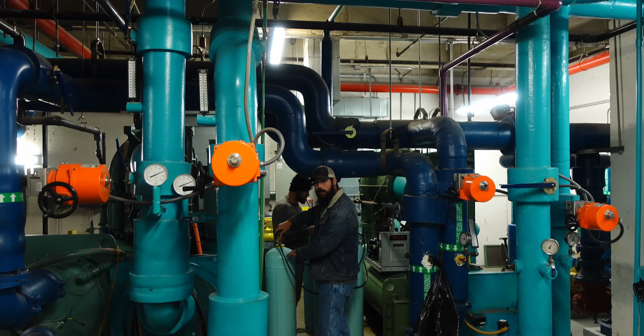Part of what I did is we pulled to a negative 10 coming into the pump. Before we completely disconnected everything, I wanted to verify and prove that we were actually completely done on the tank, since sometimes these tanks can pull into a little bit of a vacuum but still have some liquid boiling off. So we let it sit for several minutes, and we were not rising in pressure at all on the suction side of the system.